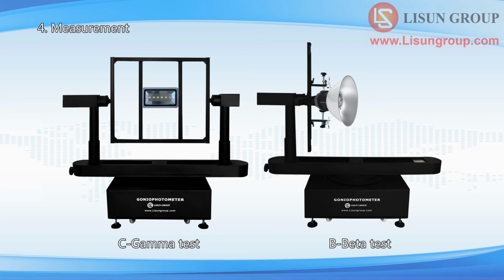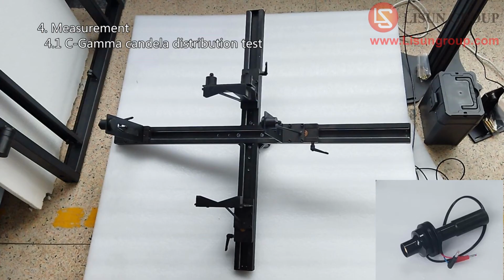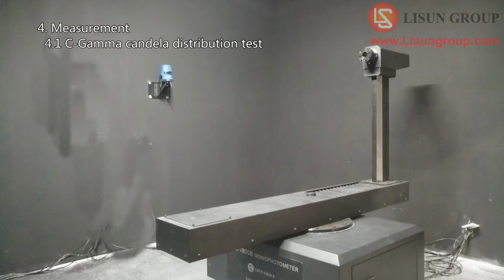LSG-1890B and LSG-1800A goniophotometers can do B-beta and C-gamma tests. Luminaires provides 2 clamps for C-gamma tests. The big cross clamp is used for big luminaires. The E27 holder is for bulbs. The assistant arm of the goniophotometer doesn't need to be installed back for the C-gamma test.